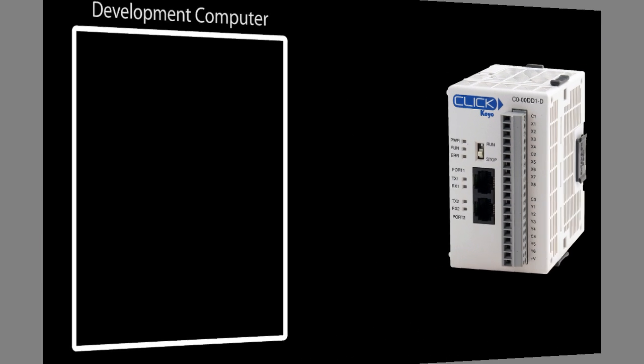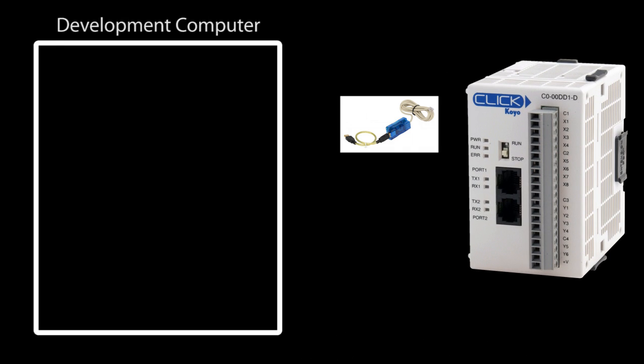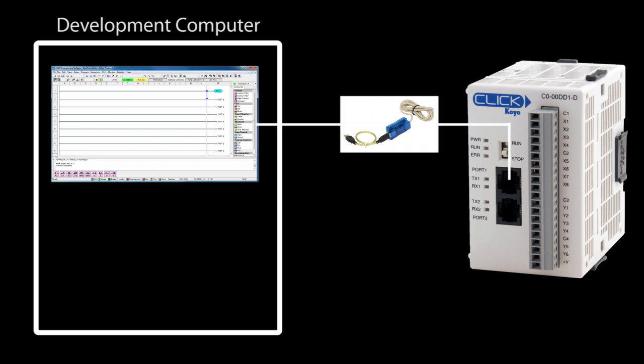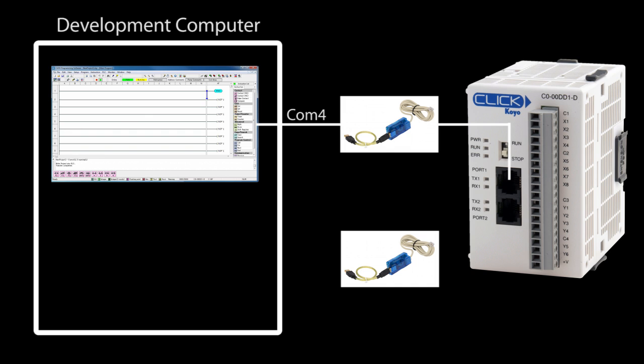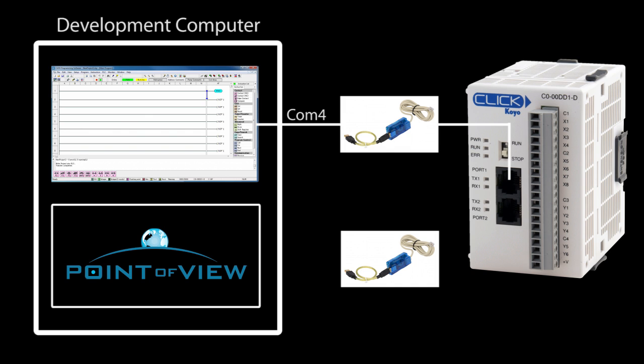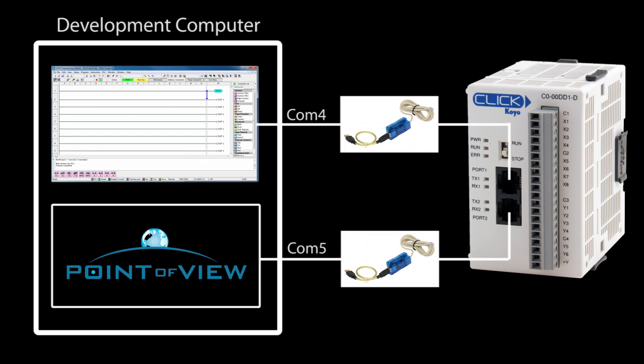So our setup looks like this. We have one USB to serial cable connecting the Click software to the Click PLC on port 1 from COM port 4 on the PC, and another USB to serial cable which Point of View will use to talk to the PLC on port 2 from COM 5 on the PC. That allows us to run both apps at the same time since two apps can't use the same serial port.